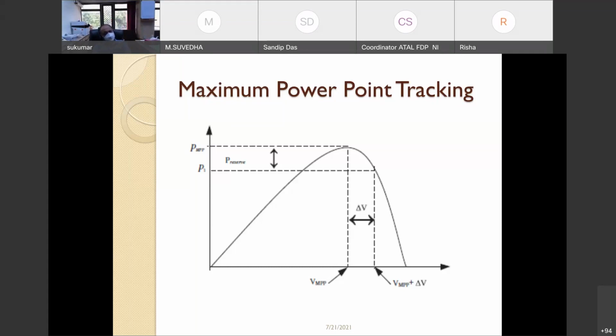Because of that, we have to produce an inertia-like response from the solar photovoltaic system. Then we can tell it to be a synthetic inertia, virtual inertia, artificial inertia. Many names can be given to it. To do that, generally we can do a derating operated system, and instead of running it at MPPT, you run it at off-MPPT operation.